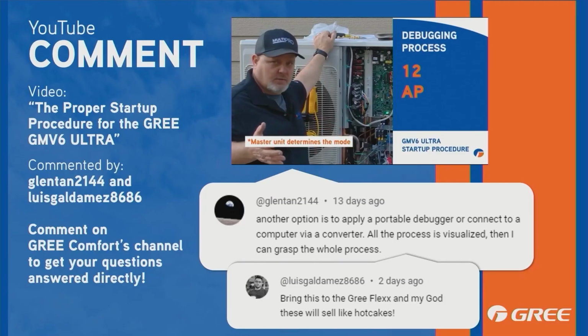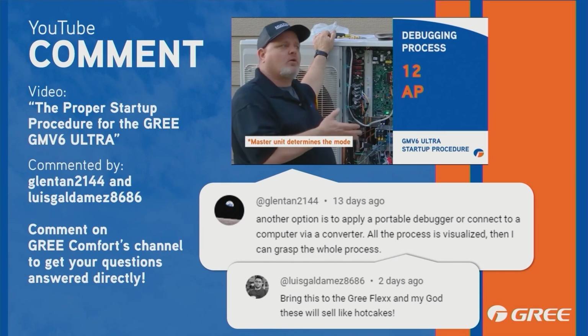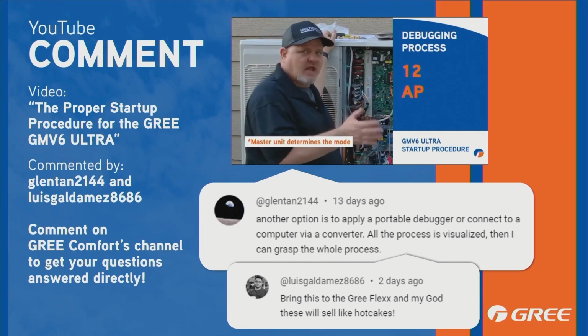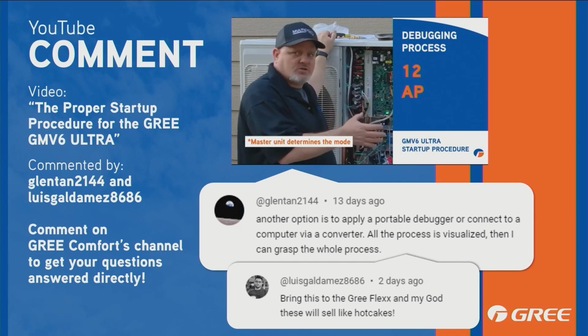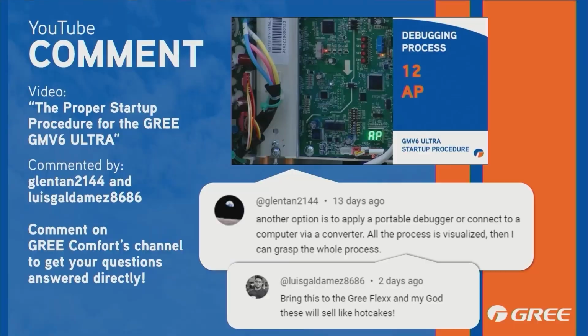For instance, like in the case of the error code you're talking about, it does a good job of telling you whether it's an indoor or an outdoor error code. So you know whether it's on an indoor unit or an outdoor unit. That was a 1-to-1 system, so it was really easy to go to on the example that I had. But had it been 1 to multiple, the error code would have only been on the machine where they miswired the condensate pump. It wouldn't have been on every single head.